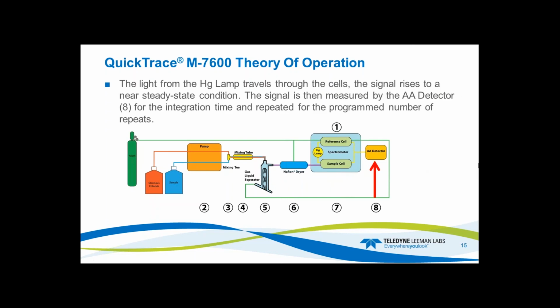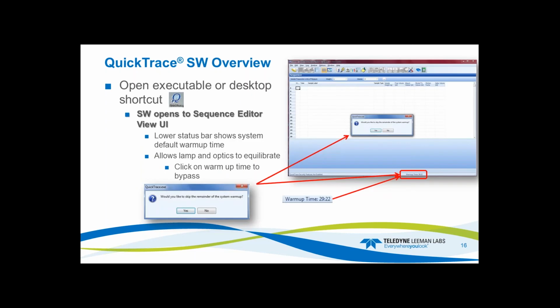So the light from the mercury lamp will travel through both cells simultaneously, so that we have a reference point for our background, which is the reference cell. Then the signal is detected by the detector, and its integration time repeats for the number of program repeats you put in the software, and it will give you an absorbance, a microabsorbance number. Moving along, quick software review.